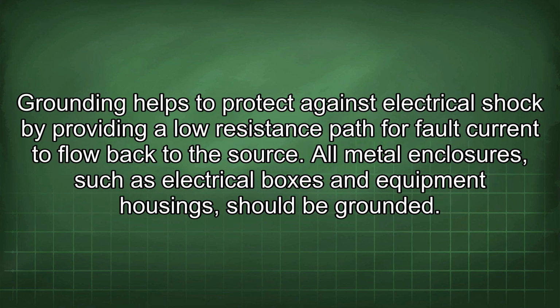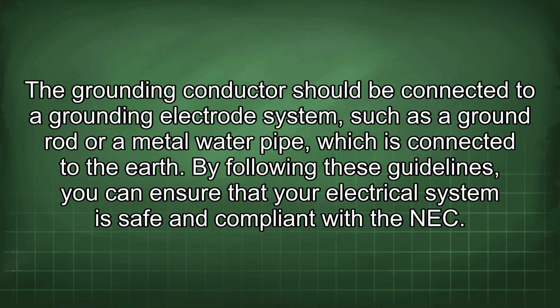Grounding helps to protect against electrical shock by providing a low resistance path for fault current to flow back to the source. All metal enclosures, such as electrical boxes and equipment housings, should be grounded. The grounding conductor should be connected to a grounding electrode system such as a ground rod or a metal water pipe, which is connected to the earth. By following these guidelines, you can ensure that your electrical system is safe and compliant with the NEC.